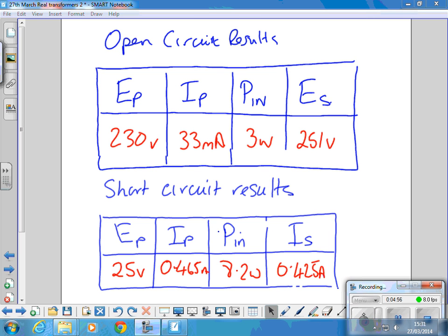Right. So, for the benefit of anyone watching the video, practical results are thus. We applied 230 volts primary voltage to the open circuit transformer. Primary current is 33 milliamps. Power in was measured at 3 watts, and the secondary voltage at the terminals 251. And the apparent step up there is where the designers of the transformer have overwound the secondary to account for the losses, to try and get this to deliver 230 at the secondary when it's fully loaded. We'll see whether that's apparent when we analyse it.